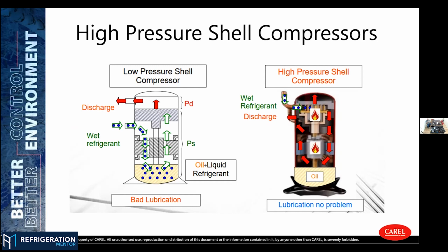So there are a few differences. I'm used to always working with low pressure shell compressors. For years and years, mostly I worked on a Copeland scroll, so that would be a low pressure shell. I know a lot of people that use the Copeland when it's low pressure. But now we're talking about this whole body, the whole shell of it, we're high pressure now. So now it's all that discharge.